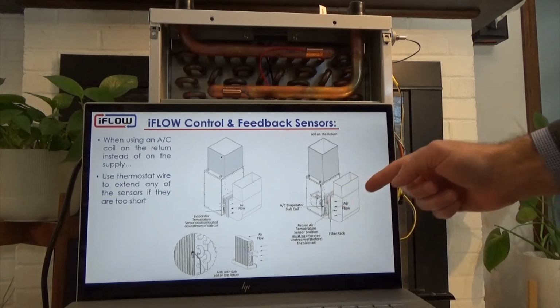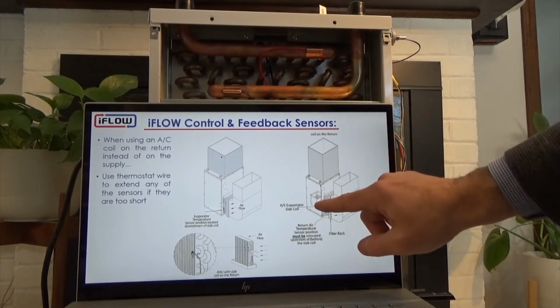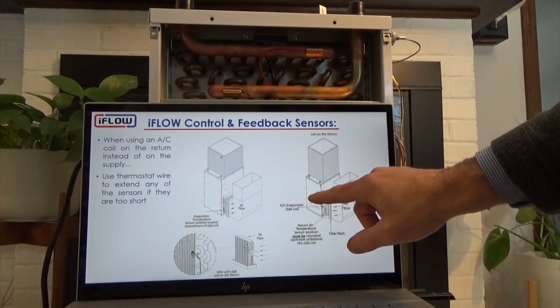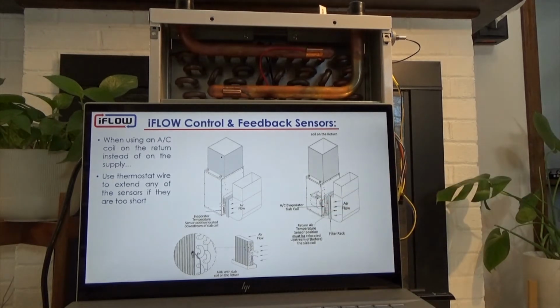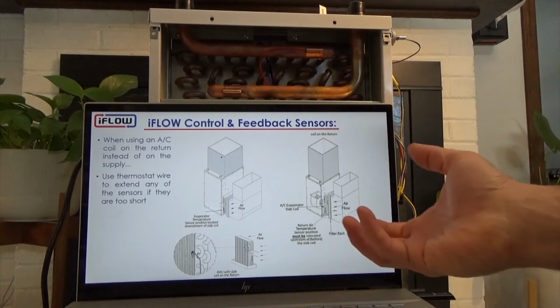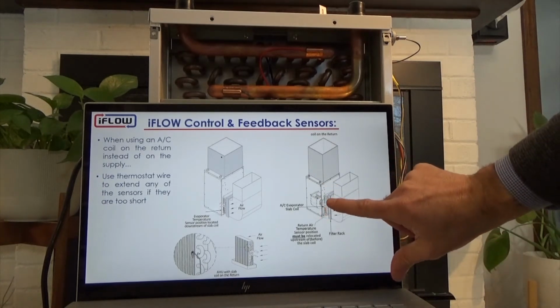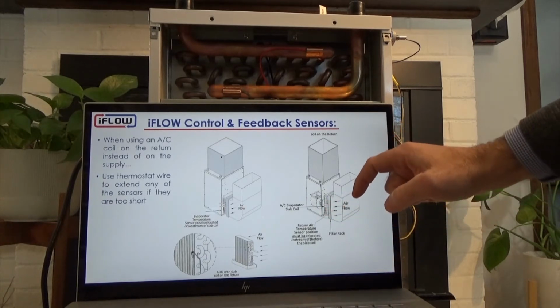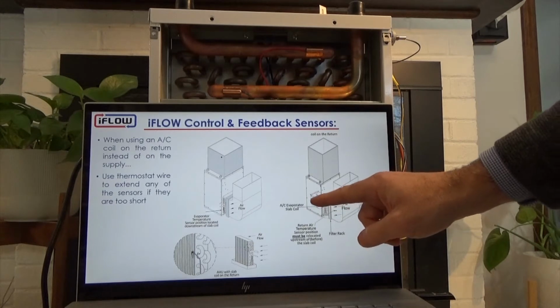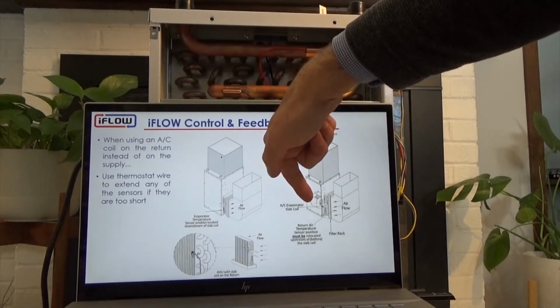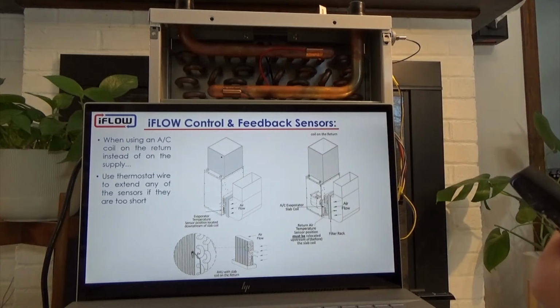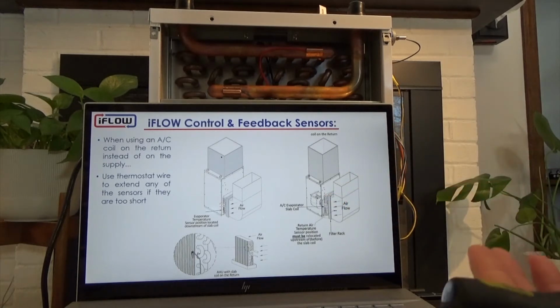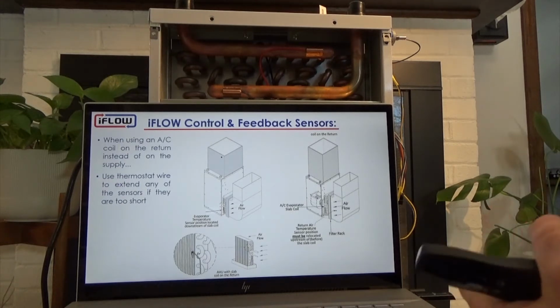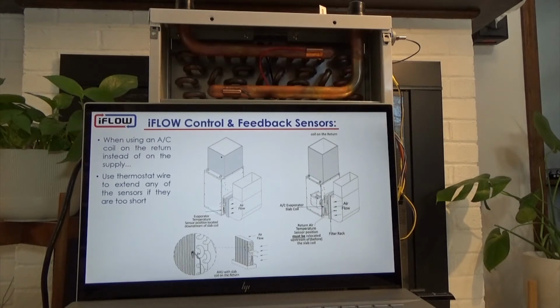So the return air temperature sensor, if we don't relocate it, which is normally located on the blower, is going to see the already conditioned air. Imagine you're calling for air conditioning, the unit will start up, the compressor will start, and you're delivering cold refrigerant to the coil. As the air passes across it, it's going to cool, and the return air sensor, which is located on the other side of the blower, is going to see that already cooled air. So you're calling for air conditioning, but the return air sensor says, well, the air coming in is already very cold, so I don't need air conditioning. It will actually turn your system off, kind of as freeze protection, almost detecting an error, if you will.